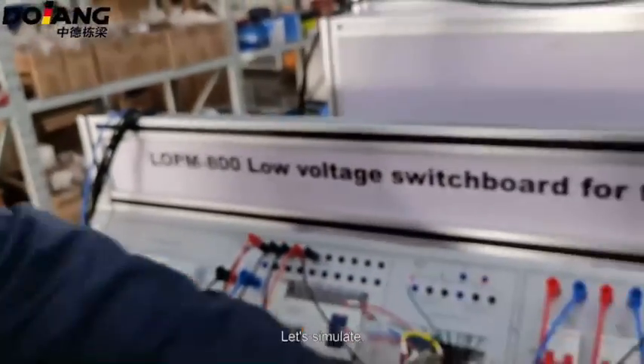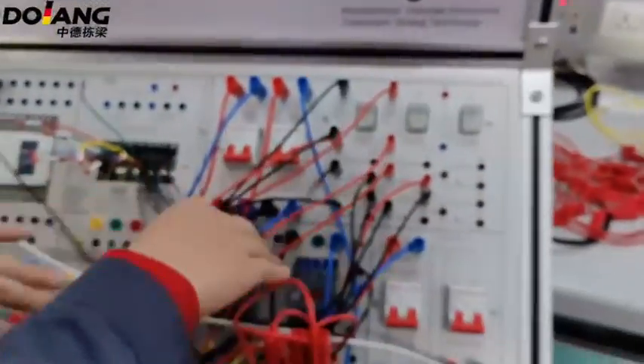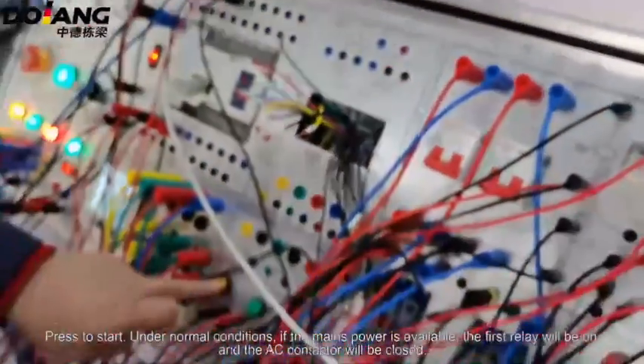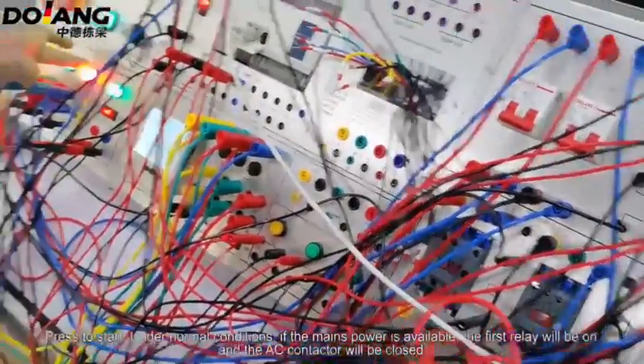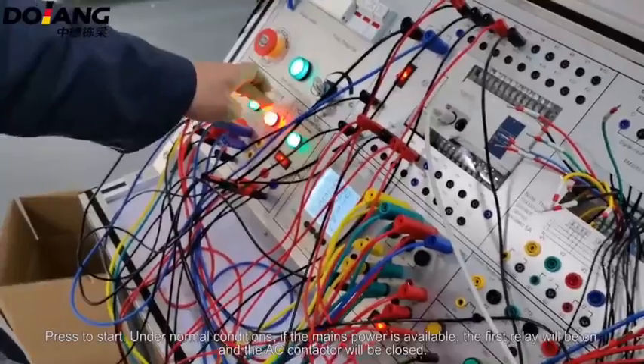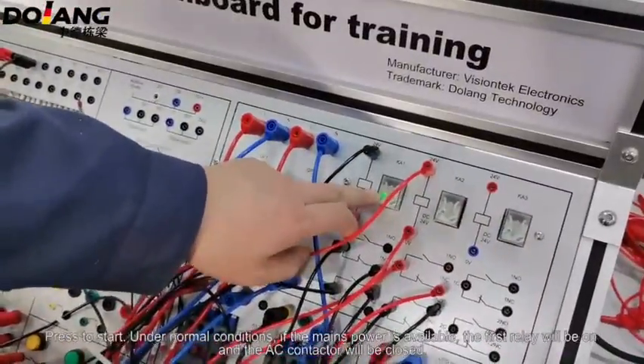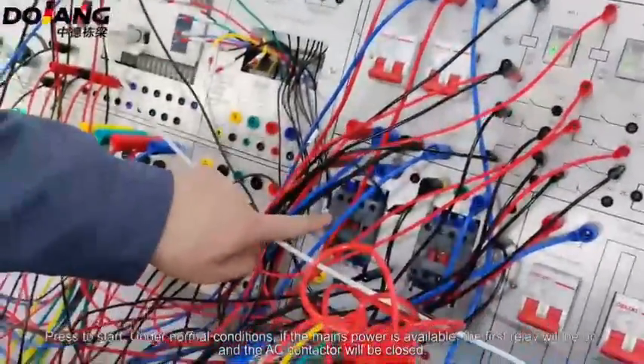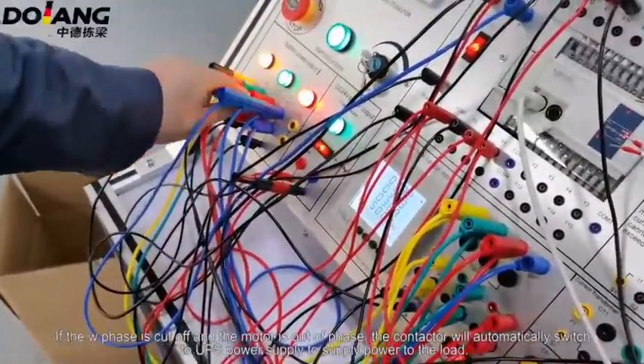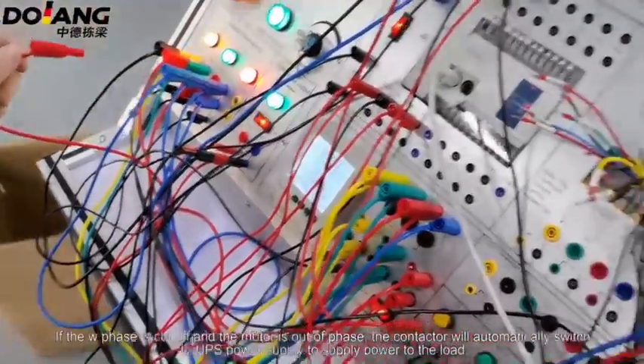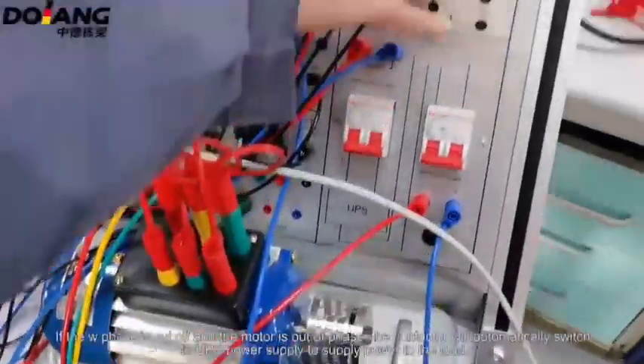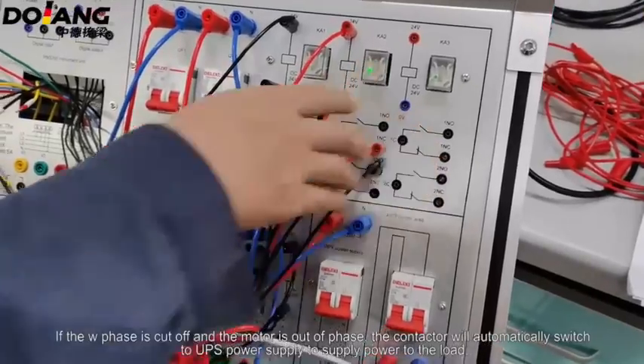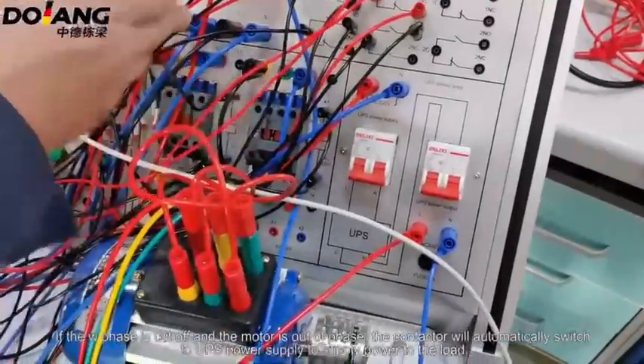Next, simulate pressing start for dual power control. Under normal circumstances, if L3 has power, the relay will light up, and the first contactor will be closed, which means normal. If a power failure is simulated, unplug L3 and the relay will automatically switch to the second one. At the same time, the second contactor is connected and the UPS power is connected to the supplied power. If L3 is powered on again, it will automatically switch back to the original state.